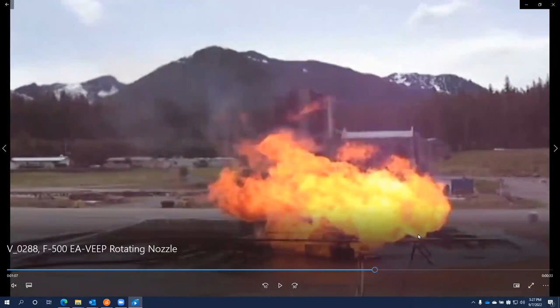So even if we're attempting to use a quality foam, say a UL 162 listed foam, we can't blanket this. Furthermore, these are pressurized nozzles spraying this LNG gas. So even if you could build a 2 meter high blanket of foam, the gas would just blow through the foam. But watch what happens here with the encapsulator agent.